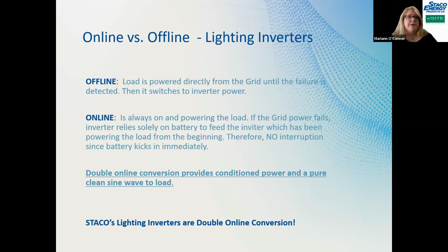In an offline unit, the inverter is not on. The battery is being charged, but the inverter isn't on. So you're not getting that conditioned power that the double online conversion unit is giving you. And then with the offline unit, as soon as the utility does go out, the inverter turns on. But all of Staco's online inverters are double online conversion. So all of our lighting inverters will condition the power and be on and provide the backup when the utility goes out, and it will keep the lights on. So, all right, next slide.